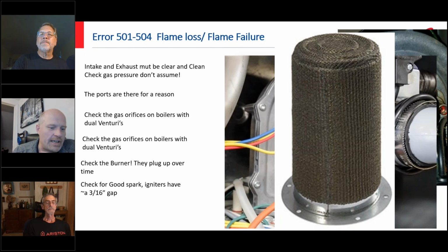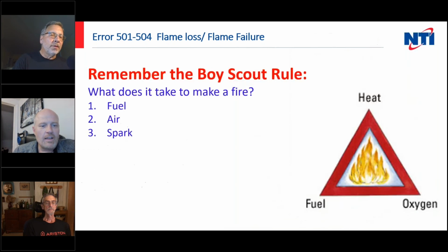Okay, check your igniters. So 3/16 gap is pretty typical. Use an Allen key to measure it. Look for warps, twists, bends, cracking. And if your boiler's lighting and running intermittently, make sure you check that combustion. It has a very big impact on how well your boiler's going to work. 2 US nickels stacked together will be 3/16.